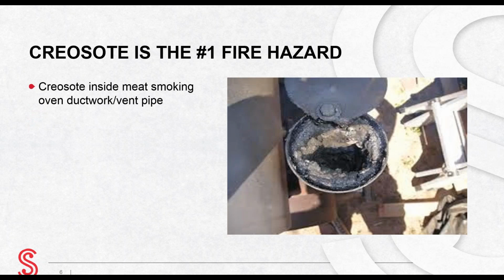The number one fire hazard associated with meat smoking ovens is creosote. What is creosote? Creosote is made up of condensed volatile gases created by incomplete combustion of wood. Wood smoke mixes with water vapor from cooking and forms creosote. Creosote clings to the interior of the oven and the exhaust system ductwork. Creosote is highly combustible and is well known for the fire threat in the chimneys of wood-burning fireplaces.